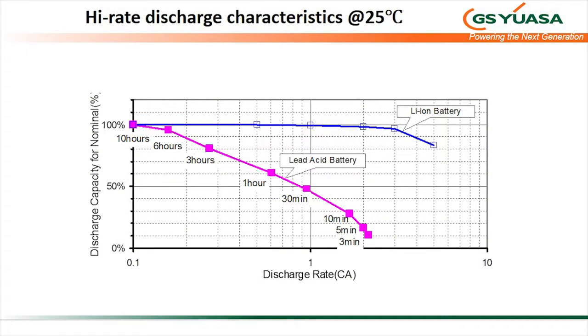The independence between power and energy is highlighted in this slide, where the pink line shows a lead acid battery, this is a 100 ampere hour battery, for instance, at the 10 hour rate of discharge. So you get 10 amps for 10 hours, which is 100 ampere hours.